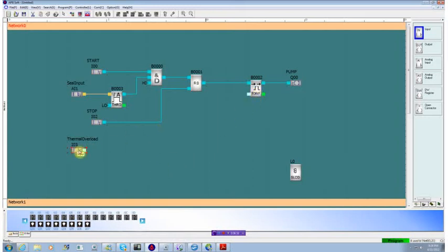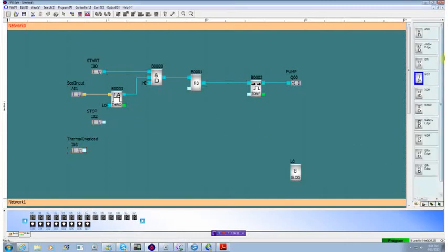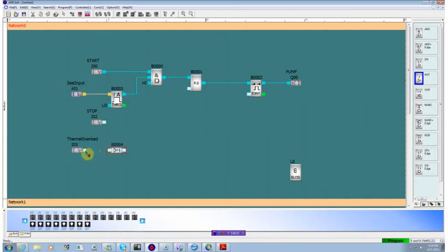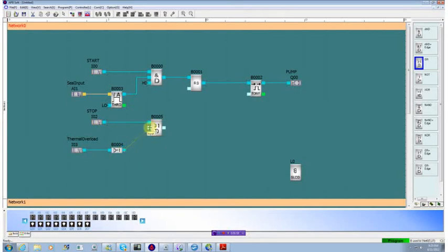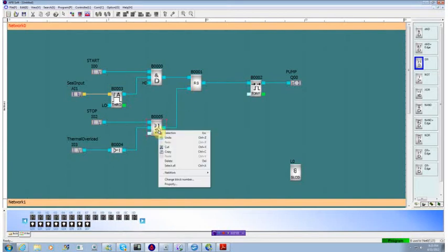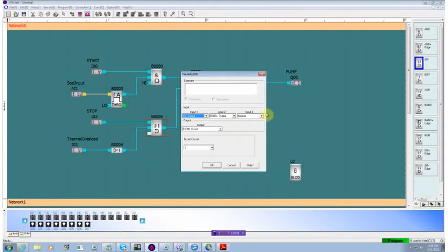Now, since it's normally closed, we're going to have to do a bit of logic here. The first thing we want to do is invert that signal so that it will go to zero when it's not active. And then we want to put in an OR gate so that if the stop happens or if the thermal overload happens, we will reset our pump. Now we have an extra input unused so we'll go in and we'll set that one to a low level because we don't want it active.